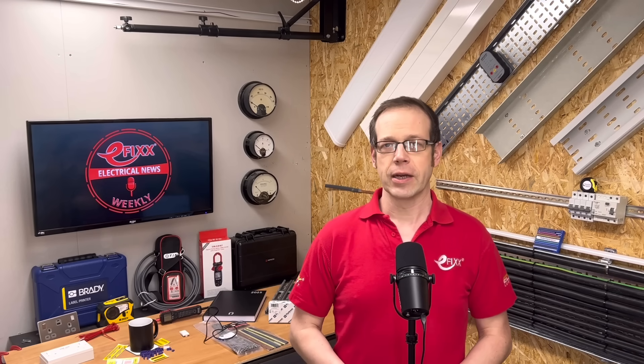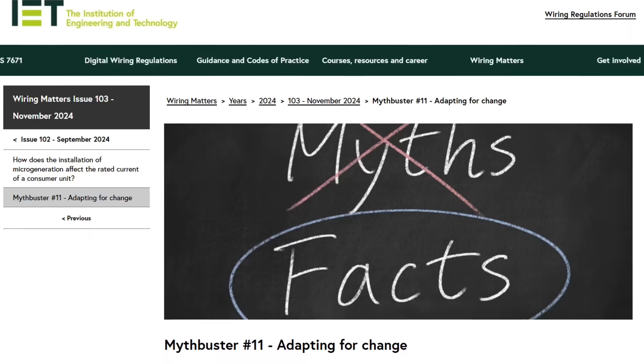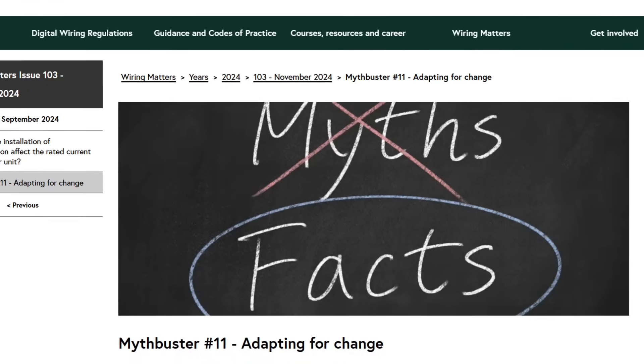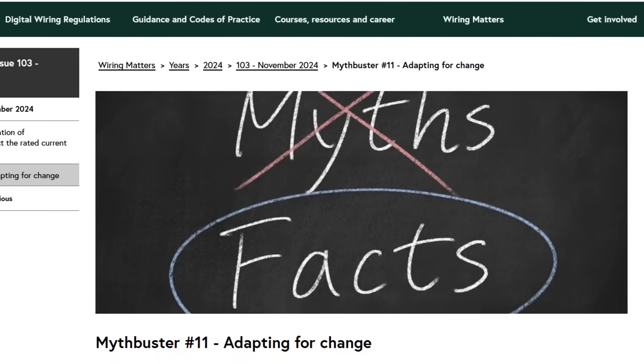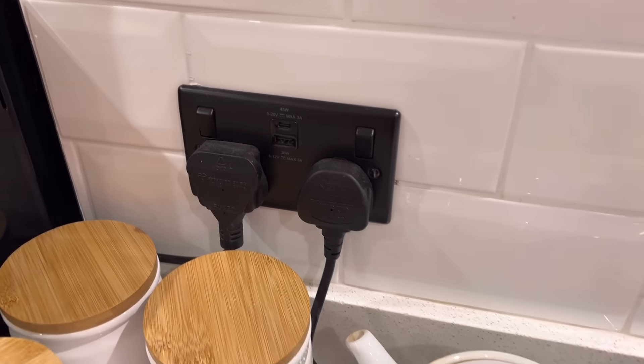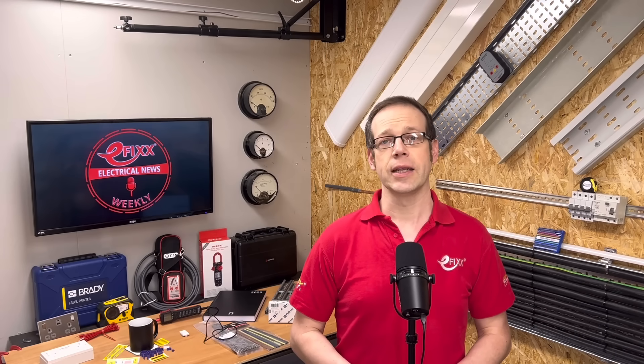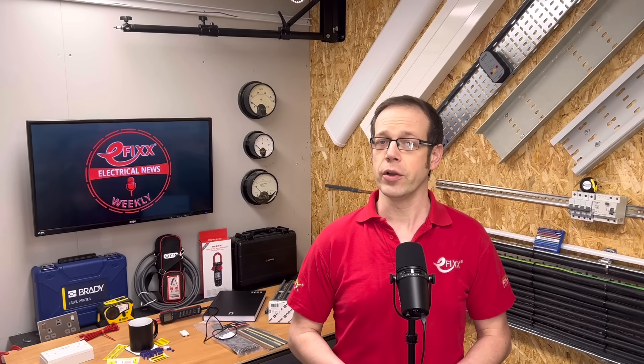The authors of the wiring regulations have weighed in on a long-time debate over cable overloading. The IET says they want to bust some myths on the topic that many electricians hold dear. They cite the example of a 1-square-millimetre twin-and-earth cable, which typically has a current rating of around 14 amps, connected to a 32-amp circuit breaker. Another is a 10-amp kettle lead plugged into a 13-amp socket. Many in the trade would label both of these as bad practice.